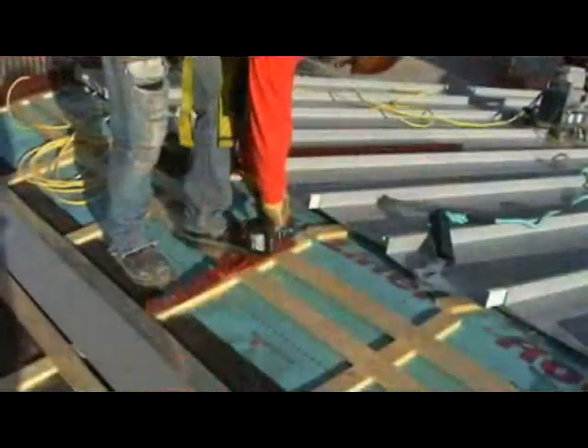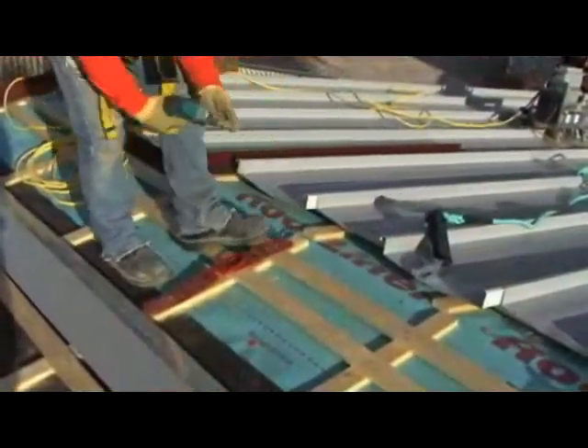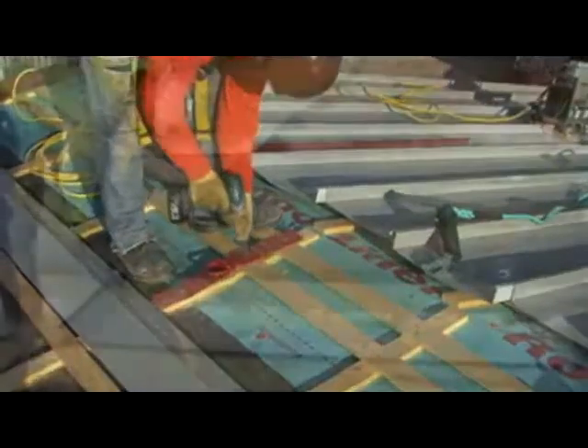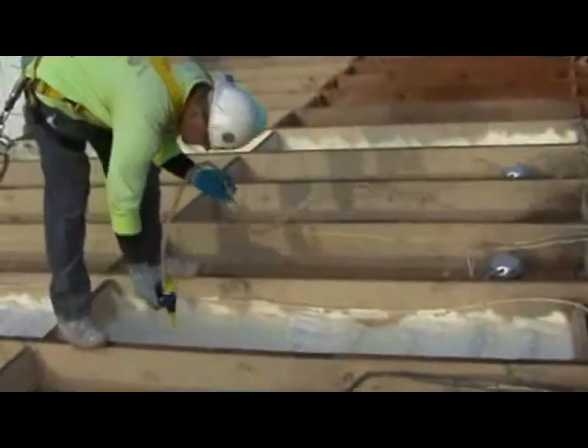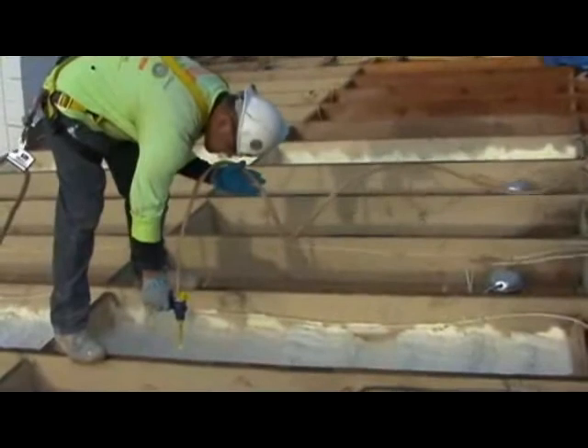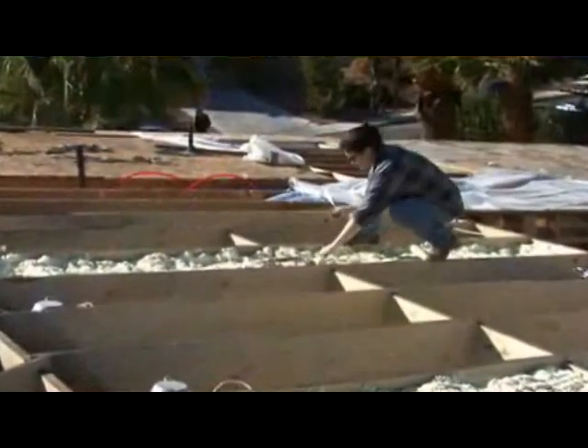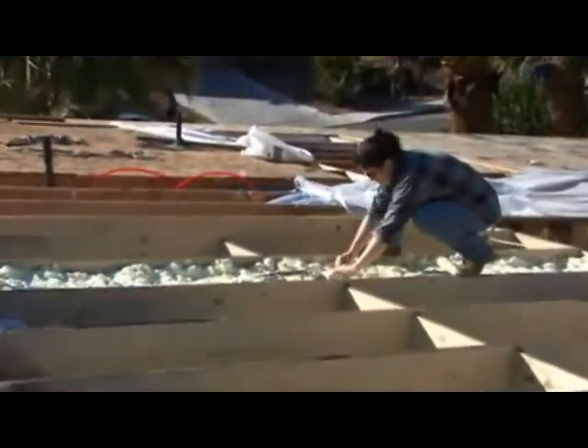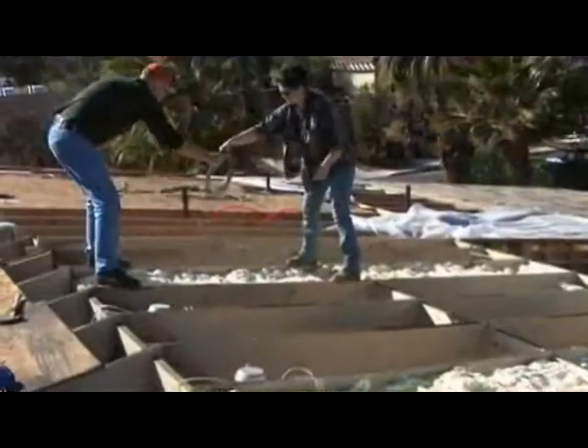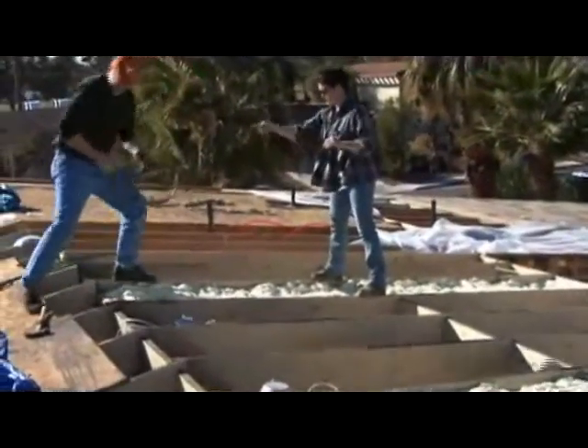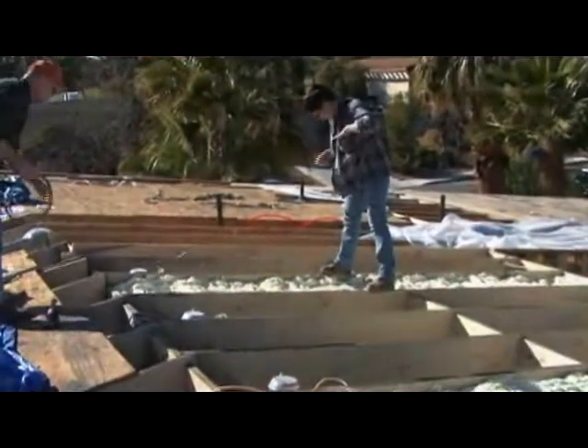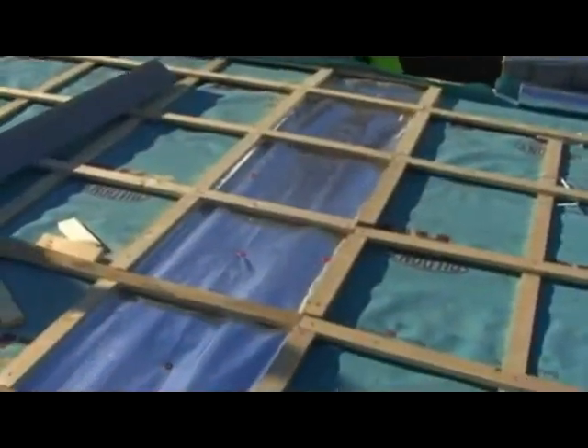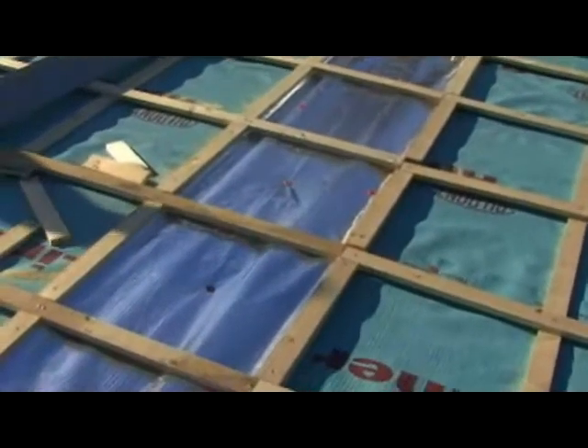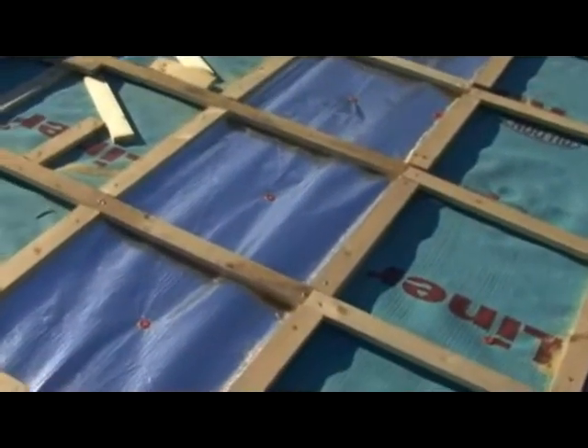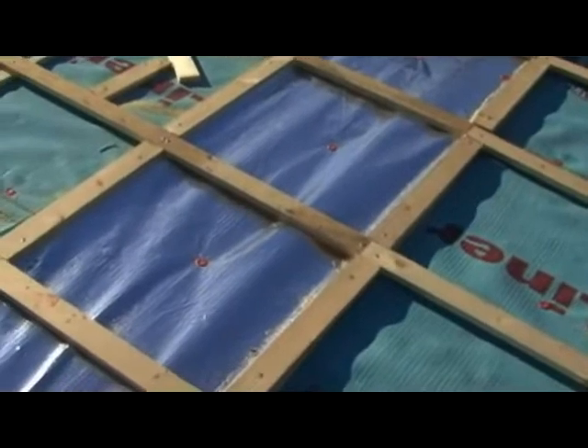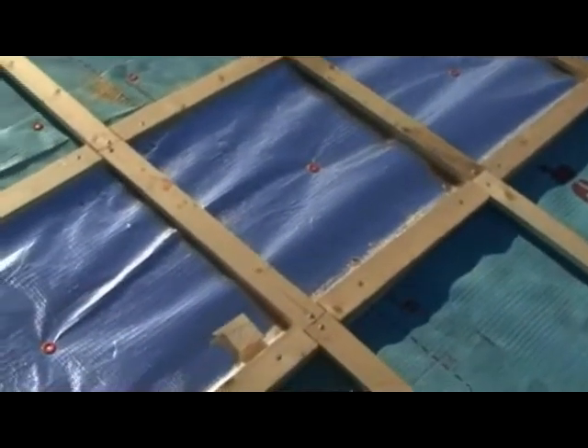Even with our work with the Metal Roofing Alliance and MBCI on this cool metal roof heat rejection strategy, we're taking this a step further to see if we can get even higher levels of performance with this roof. Under 2 of the roof panels, we've got thermocouples mounted, trying to see if we can lower the temperature on top of the roof insulation even further by employing a radiant barrier facing up into the vented space. We'll be collecting data over the summer, checking the temperatures in those 2 test bays to see if that additional radiant barrier can lower the temperature of the roof cavity even further.